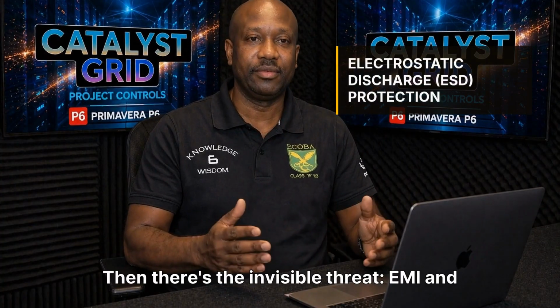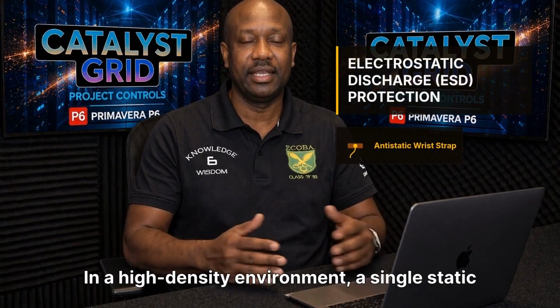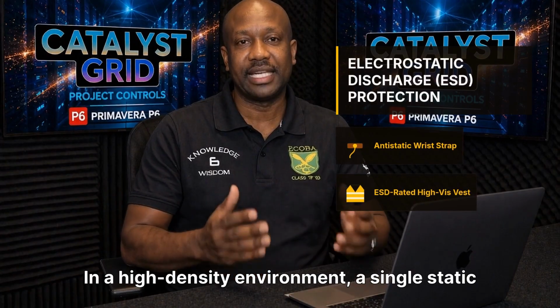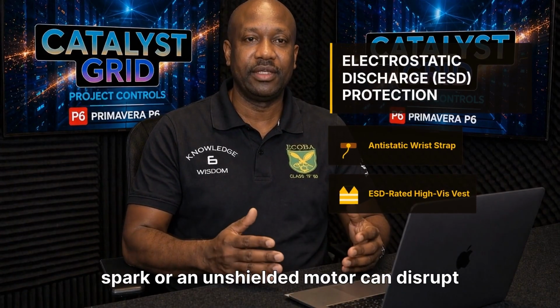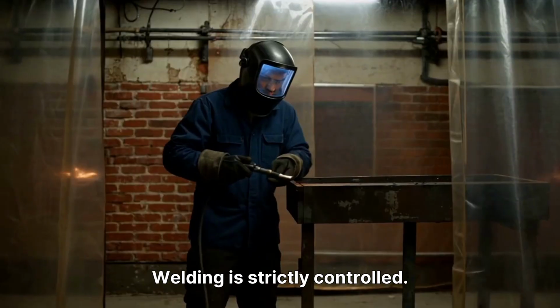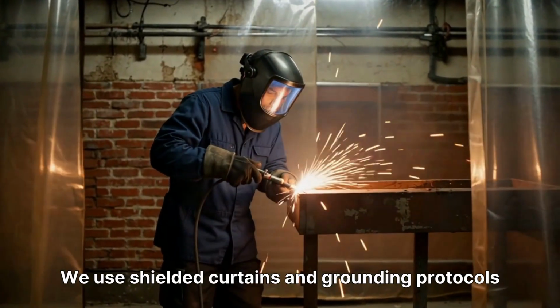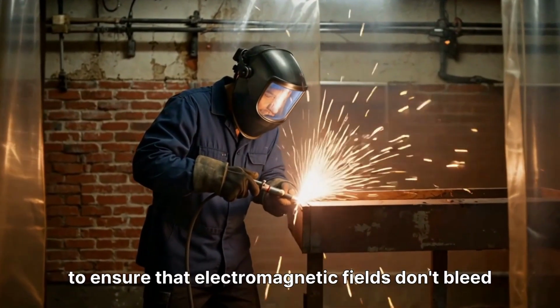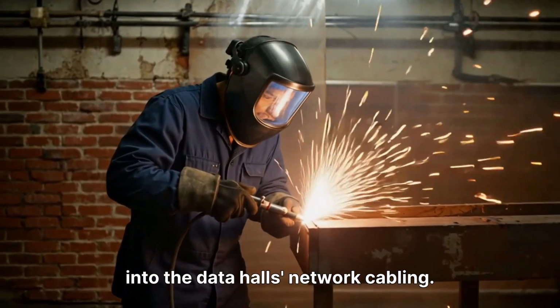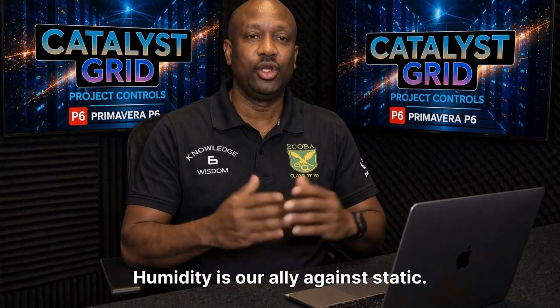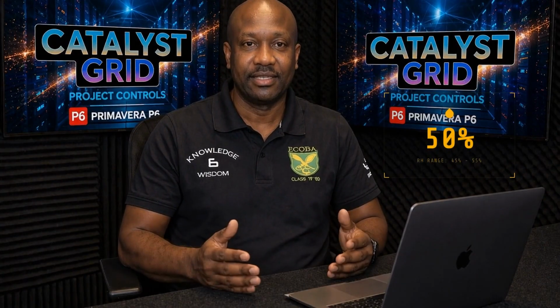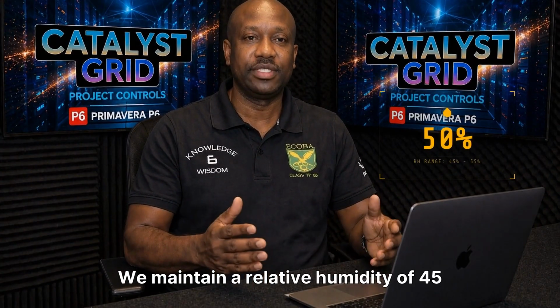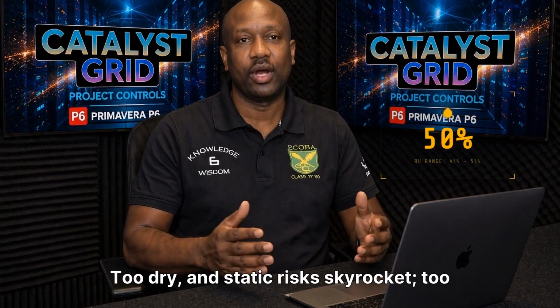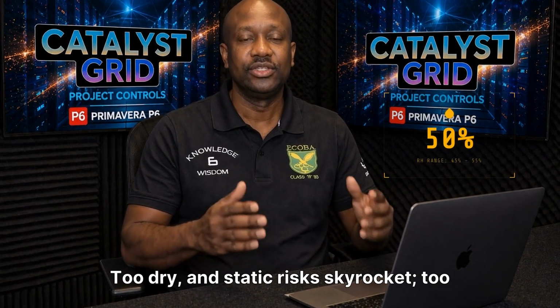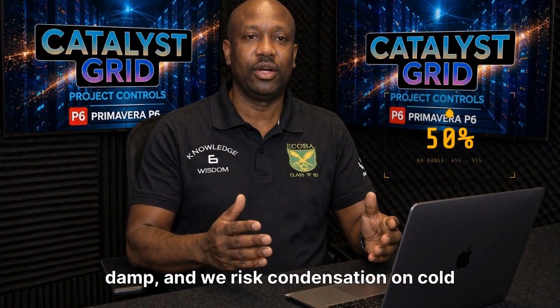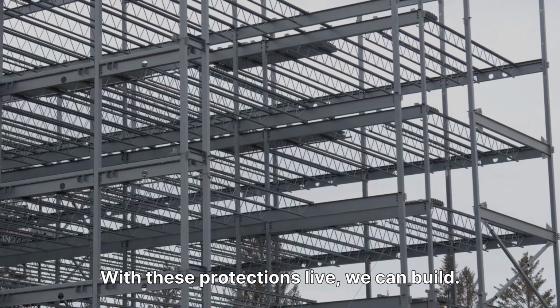Then there's the invisible threat, EMI and ESD. In a high-density environment, a single static spark or an unshielded motor can disrupt communications. Welding is strictly controlled. We use shielded curtains and grounding protocols to ensure that electromagnetic fields don't bleed into the data hall's network cabling. Humidity is our ally against static. We maintain a relative humidity of 45 to 55%. Too dry and static risks skyrocket. Too damp and we risk condensation on cold aisles. With these protections live, we can build.